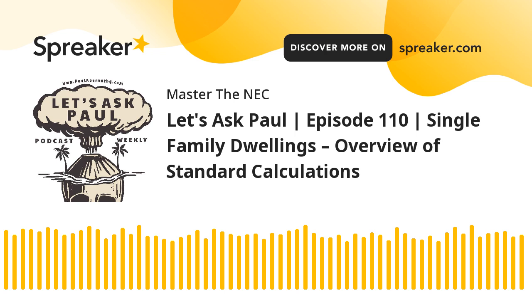But the VA value that you're going to use for this calculation, that's covered in 220.52(B). And that's pretty much the same as your small appliance branch circuit. It's 1500 VA shall be included for each 2-wire branch circuit installed as covered in 210.11(C)(2). Now remember, 210.11(C)(2) only requires at least 1. In the real world, if you've got more than 1, then you need to take that into consideration. It would be 1500 VA for each one of those that you want to have or your customer wants to have. As far as exam prep, if they don't tell you the number, then you at least have to have the minimum, and it's at least 1.